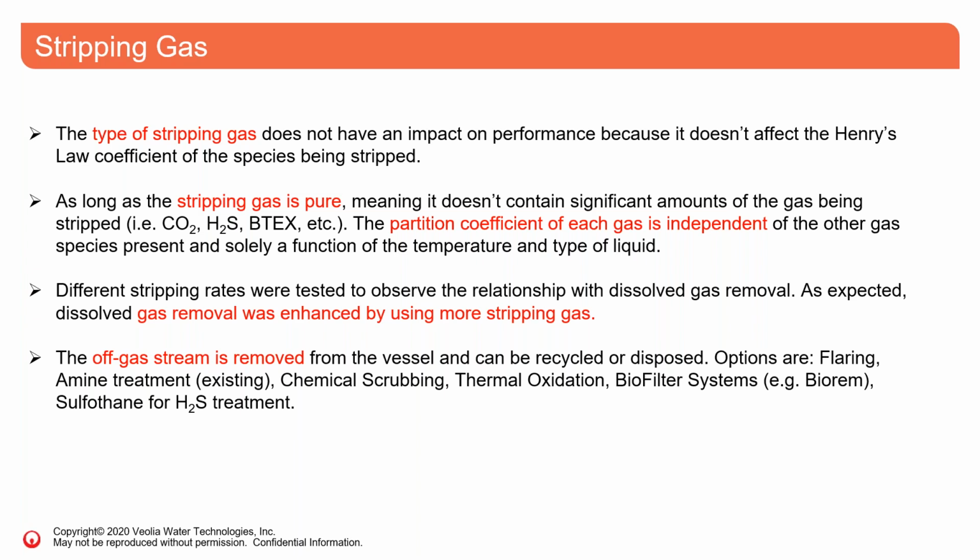The off gas that is removed from the vessel can either be recycled or disposed. Some of the options are flaring, using existing amine treatment, chemical scrubbing, thermal oxidation, biofilter systems, or SulfaTreat for H2S treatment.